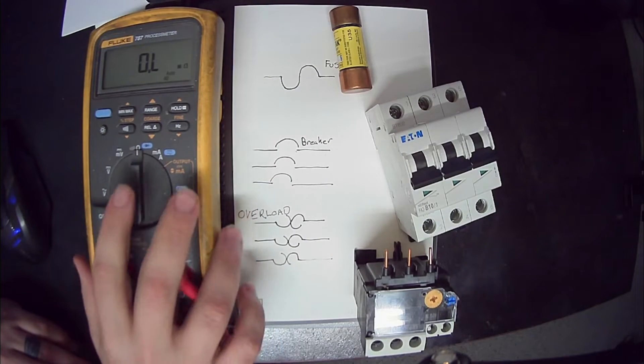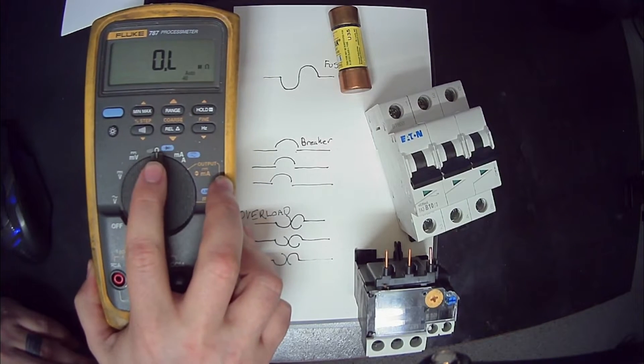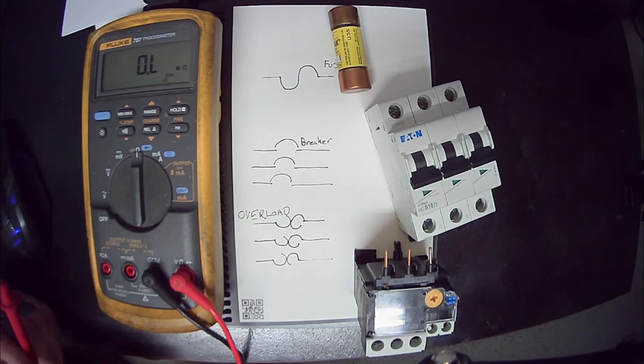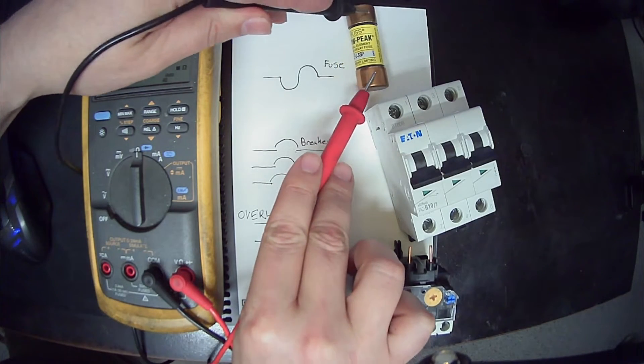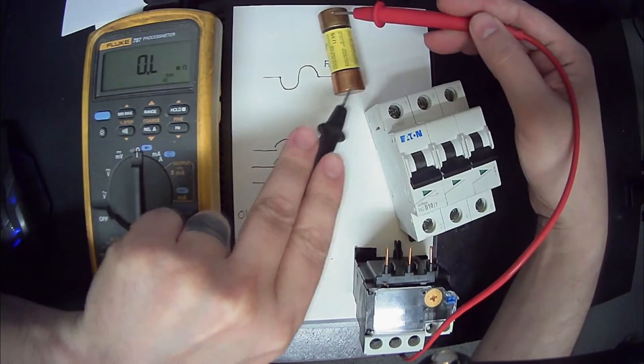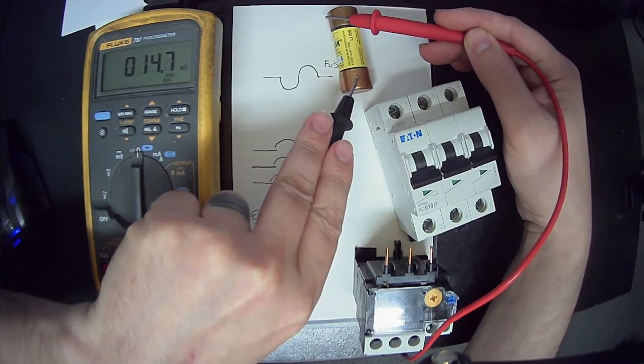So how do we test it? Outside the system, we're going to take our multimeter to our ohm setting, jump right in here, and all we're doing is testing across the device. That's all we're doing. What we want to see is very, very low resistance.